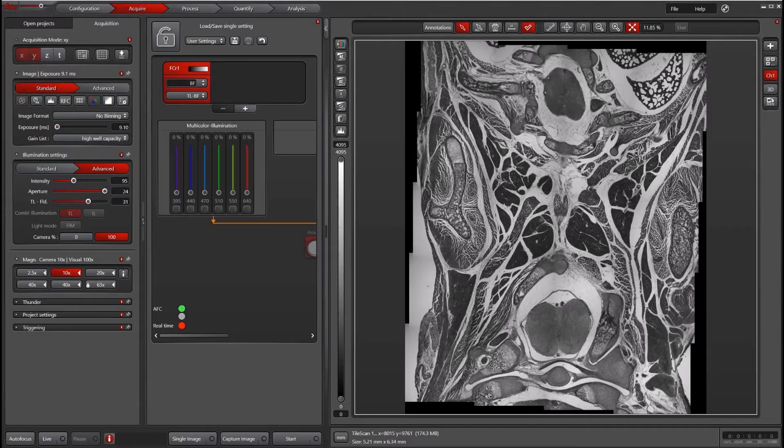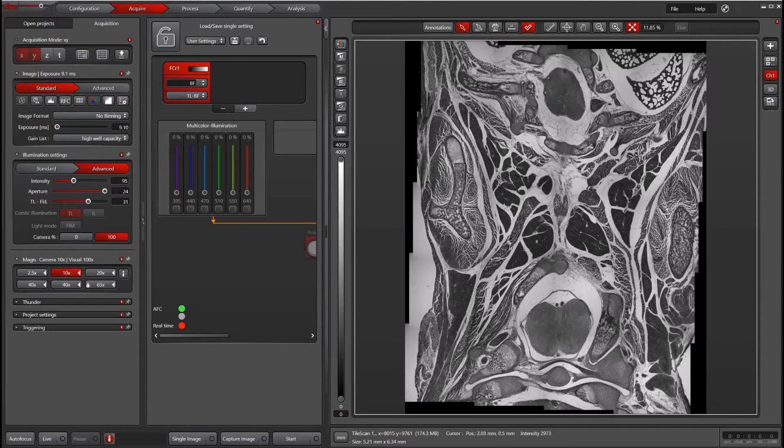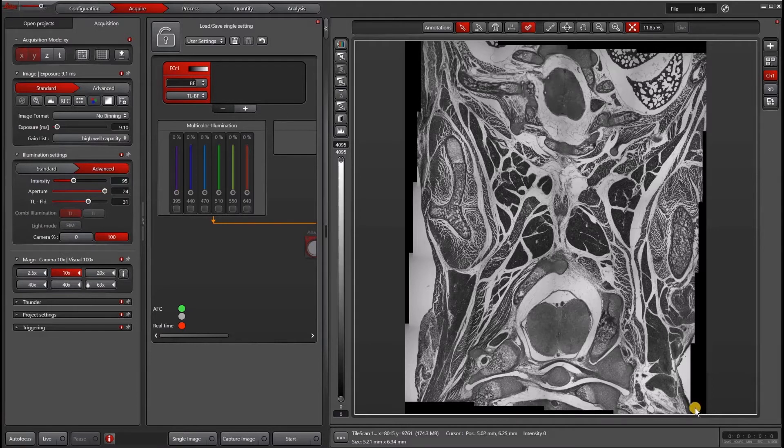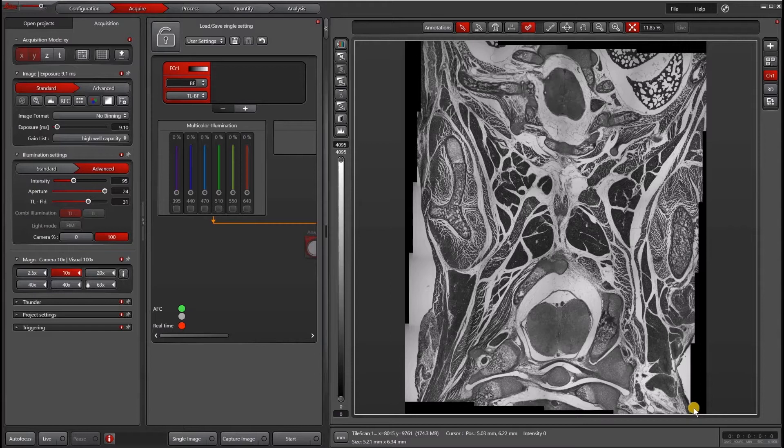Here's a nice example of what happens if your camera isn't aligned properly. When you do a mosaic or tile scan, you get these jagged edges on the sides of your images. Sometimes if it's really not aligned properly, you won't even get good matching for the stitching. So it's really important to make sure that your camera is aligned properly.